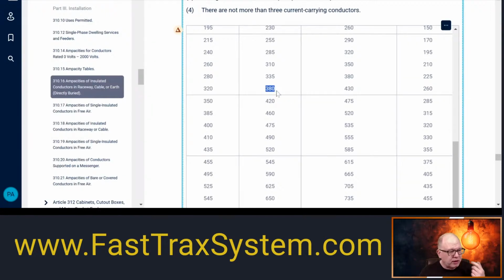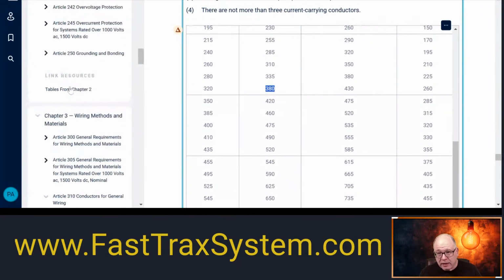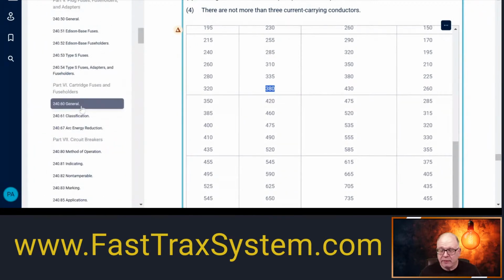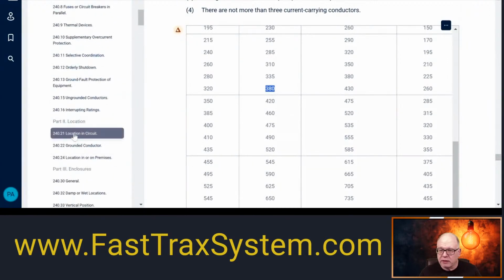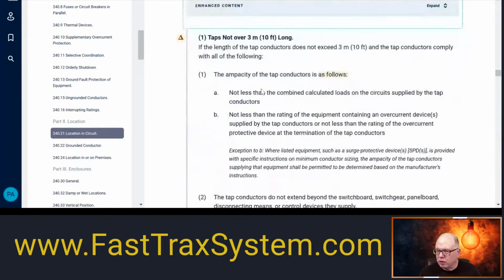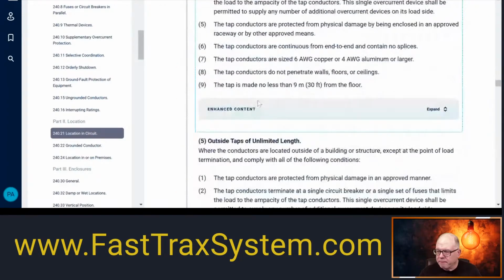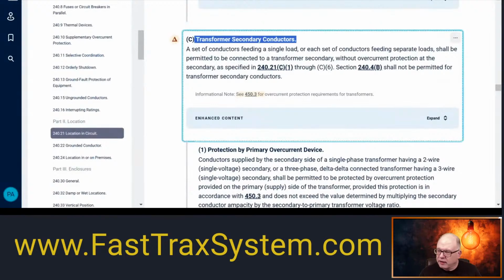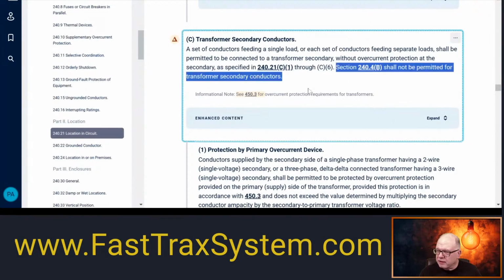So it's 380 amps. Now, the question that people ask is, well, if it's 380 amps, can I use the next size up rule and terminate that on a 400 amp overcurrent device? And the answer to that is no, you cannot. And people say, well, where does it say that I cannot do that? Well, we have to go back to 240.21. And if we come down here to C, because we're doing secondary conductors, it says right here that section 240.4(B) shall not be permitted for transformer secondary conductors. So that is the rule, okay? So that's what we're into when it comes to that.